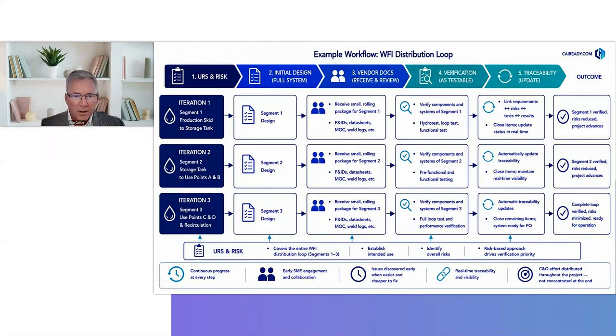This slide shows how iterative C&Q works when applied end-to-end on a real project. The URS is developed early to establish intended use with the understanding that it may evolve as design choices mature and risks are refined. These changes are controlled, traceable, and deliberate, not ad hoc revisions. Vendor documentation is submitted in smaller, rolling packages rather than large batches. Subject matter experts review documentation immediately while context is high and vendor engagement is active. This improves review quality and reduces rework. Verification is executed as soon as elements become testable. That may be at the component level, subsystem level, or functional level, depending on risk.